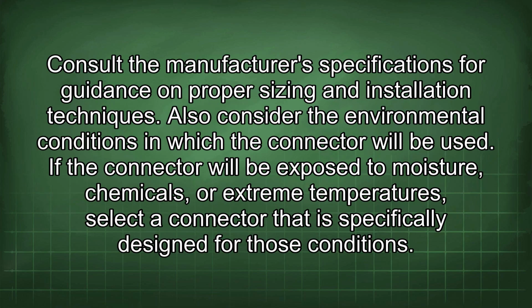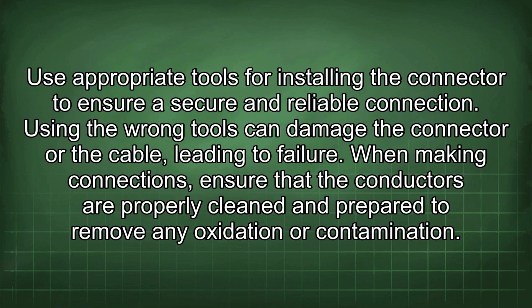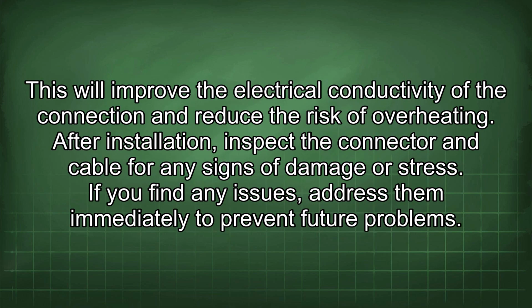Consult the manufacturer's specifications for guidance on proper sizing and installation techniques. Also consider the environmental conditions in which the connector will be used. If the connector will be exposed to moisture, chemicals, or extreme temperatures, select a connector that is specifically designed for those conditions. Use appropriate tools for installing the connector to ensure a secure and reliable connection. Using the wrong tools can damage the connector or the cable, leading to failure. When making connections, ensure that the conductors are properly cleaned and prepared to remove any oxidation or contamination. This will improve the electrical conductivity of the connection and reduce the risk of overheating.